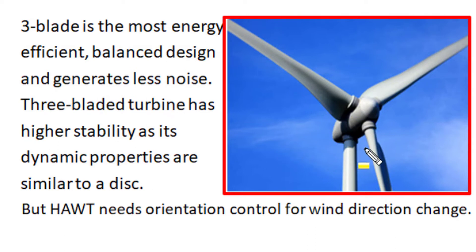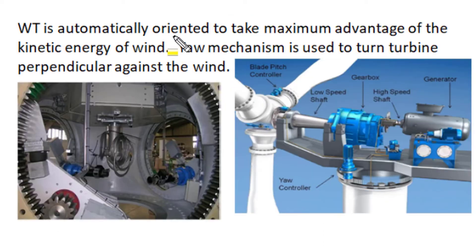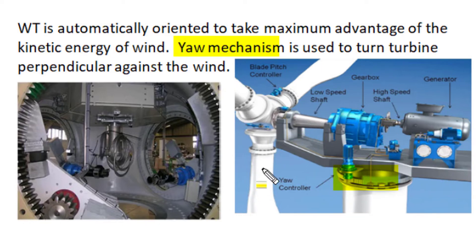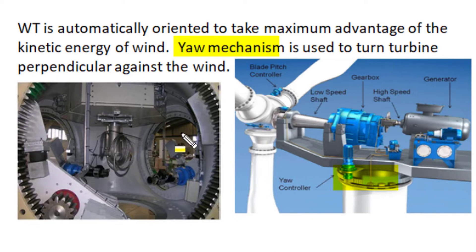All horizontal axis wind turbines need orientation control when the direction of wind changes, to harness wind energy at the optimum level. A yaw mechanism is provided on top of the tower, attached to the nacelle bed. This yaw mechanism is used to turn the nacelle bed such that the turbine gets its orientation perpendicular to the direction of wind blow, enabling it to take maximum advantage of the kinetic energy of the wind.